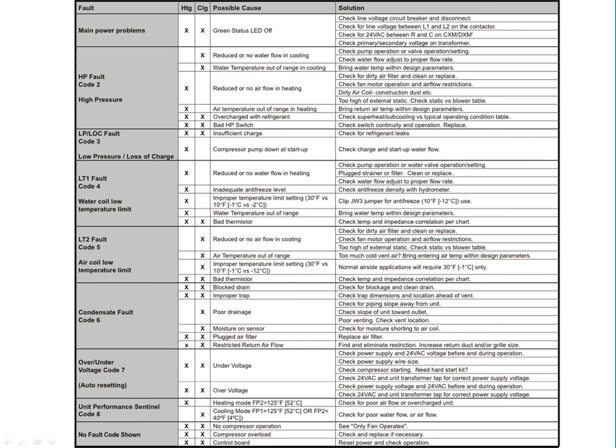Again, in that same vicinity, we just referenced that ohms resistance chart, guys. There's a menu here of the fault codes on the left, what they mean, and if you look, there is a heating or cooling, whichever mode you're in, then it tells you what the possible causes could be, and if you look to the right of each one of those fault codes, you're going to see possible solutions. Guys, this is critically important that you have your All Products Technical Guide with you to make sure that you have the ability to see this.